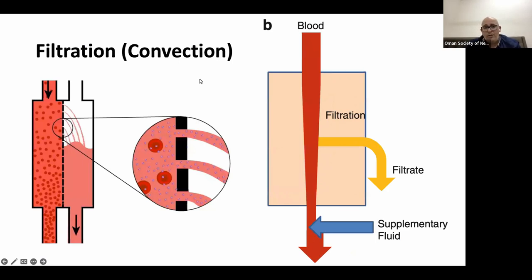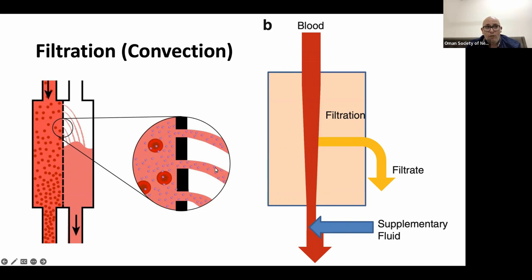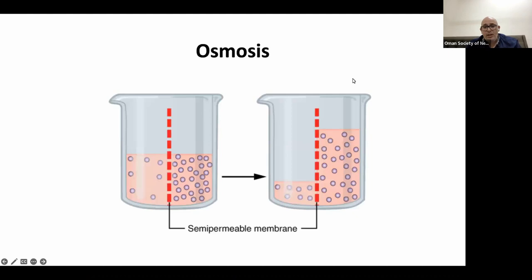The next technology is filtration — the convection process. Unlike diffusion, it is not passive; it depends on hydrostatic pressure that compresses blood against the filter membrane to move solutes non-selectively up to a certain molecular weight limit. Because the filtrate comes out, the blood decreases in volume, so supplementary replacement fluid is required after that.